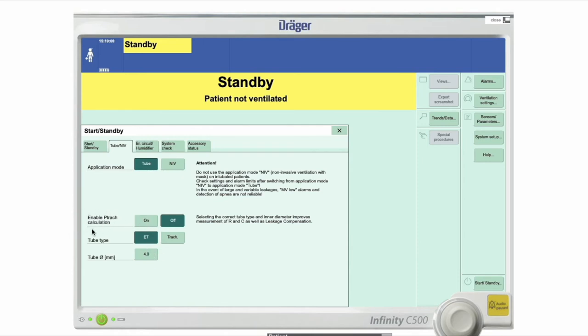Now there's this other interesting button here: enable Ptrach calculation. If you switch this on, you're saying you want the ventilator to attempt to calculate the pressure at the end of the trachea. The usefulness of this is that if you calculate that figure in the first place, it's easier for the ventilator to get more accurate resistance and compliance data, and it also makes it easier to assess leakage compensation. So as far as I'm concerned, it should be on all the time. This is what it should look like if we're ventilating a 10 kilo child.